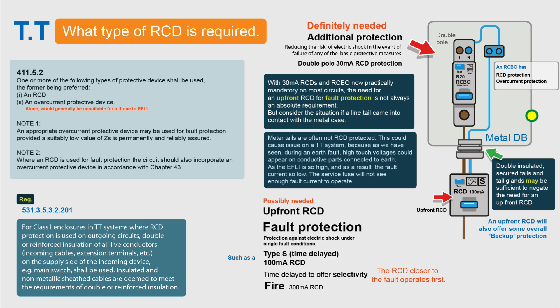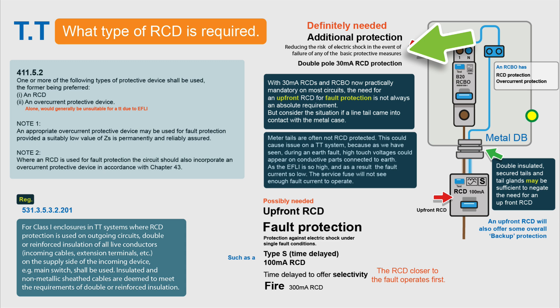TT systems have always required some form of fault protection. It used to be voltage-operated earth leakage circuit breakers, then that moved on to RCDs. We now have RCDs on every circuit, but it used to be that you had one up-front RCD. That can cause nuisance tripping issues — if it goes off you lose power to the whole house — so they had a time-delayed RCD rated at 100 milliamps to provide fault protection. You can have an RCD for fault protection and an RCD for additional protection. Fault protection is protection against electric shock under a single fault condition, while additional protection reduces the risk of electric shock in the event of a failure of basic protective measures. The vast majority of circuits now require this additional protection of a 30 milliamp RCD, so the requirement for an up-front RCD for fault protection is not absolute but depends on the installation's requirements.